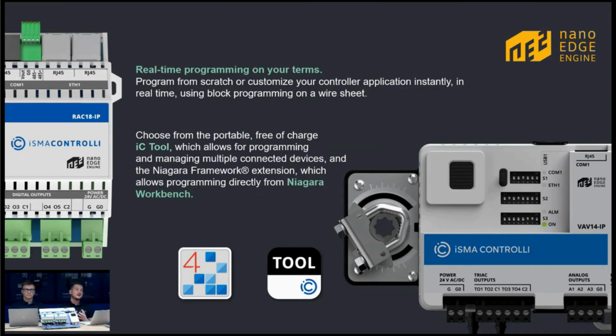But at the same time, we created a special Niagara framework extension for our controllers that will allow not only integrating the devices in Niagara framework, for which we will use Modbus or BACnet, but will also give you the capability of configuration of the controller with the IP address, backups, application creation using the Niagara wiresheet, and of course, the whole commissioning process and integration. So this is what we have for you.